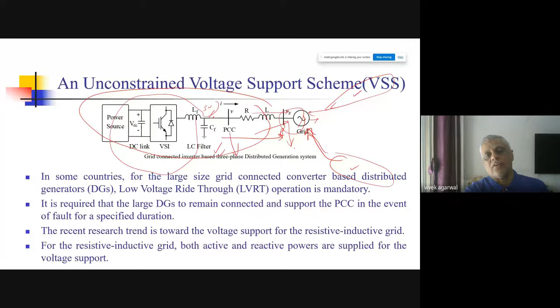So to prevent this collapse, the sudden unstable situation, it is required in the LVRT that the system actually remains connected to the grid for at least a few seconds. Of course, that number of seconds varies from country to country and standard to standard. But let's say 1 or 2 seconds or 4 or 5 seconds, and during that time feed reactive power. So remember, feeding reactive power, whether you see the conventional generator or what I just explained to you about the voltage frequency control, I told you that if you feed reactive power, your voltage should stabilize.